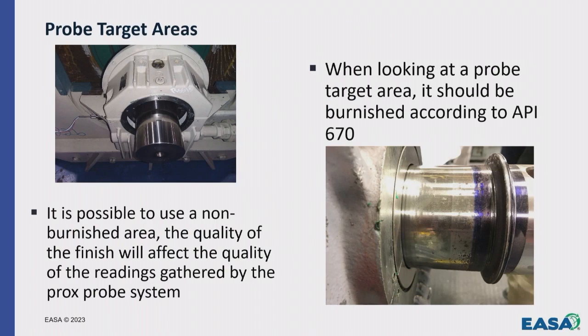The picture at the top left, you'll see that's got a nice, shiny, almost mirror-like finish. A properly burnished probe area is going to look like a mirror. It's going to be very smooth, very clean. It's going to be almost too smooth, look almost chrome. It's possible to use a non-burnished area, but you're not going to get the level of accuracy. You're going to get a few more defects or noise in your signal on the back end.